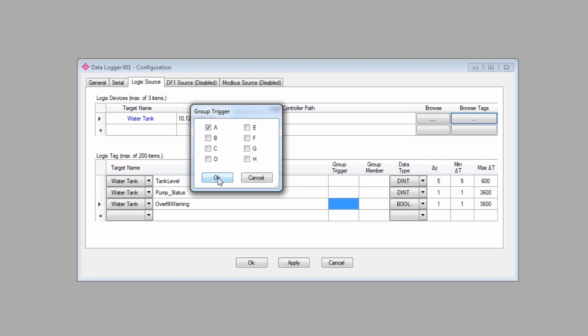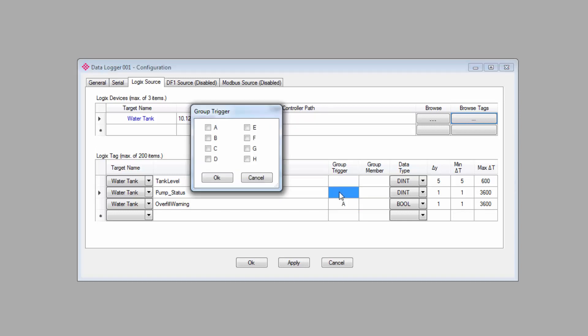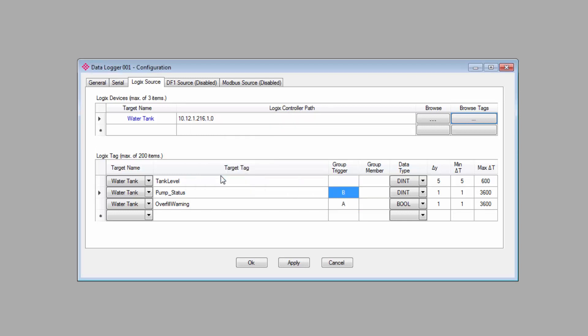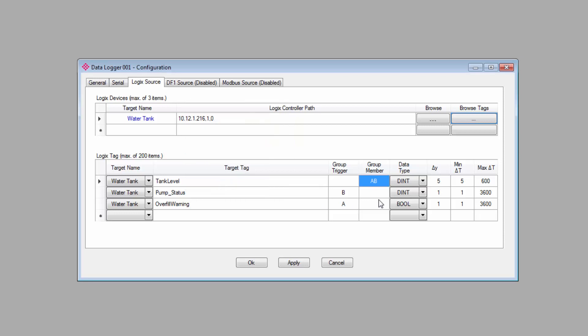And what I can do is assign the overfill warning to group trigger A and the pump status to group trigger B. Then, I'll make the tank level tag a group member for A and B. So now, anytime the pump turns on or off, it will trigger a log for all members of group B. Likewise, anytime the warning is tripped, it will trigger a log for all members of group A.